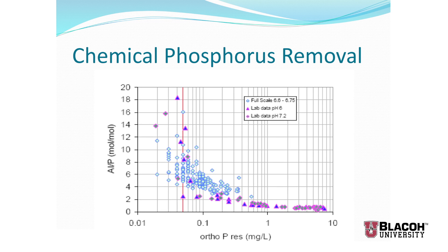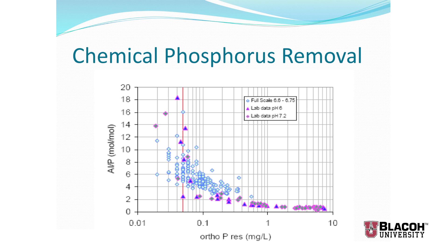If you need to remove more phosphorus — say down to 0.05 mg/L residual, which is a limit some plants in the United States must achieve — that's the red line on the graph. To reliably reach that level, you may have to add as much as 16 times as much aluminum as there is phosphorus. This can produce a large amount of solids settling in your clarifier or being filtered out. Combined with the metal hydroxides from reacting with hardness, solids removal becomes a big part of a chemical phosphorus removal system.